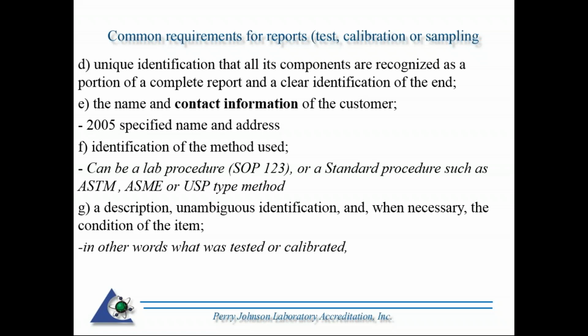F, identification of the method used. What was the procedure? It could be an internal procedure, your laboratory's internal SOP number. It could be a nationally recognized procedure such as an ASTM, ASME, or USP type method. Whatever procedure was utilized in doing the particular test or calibration needs to be specified on the report.